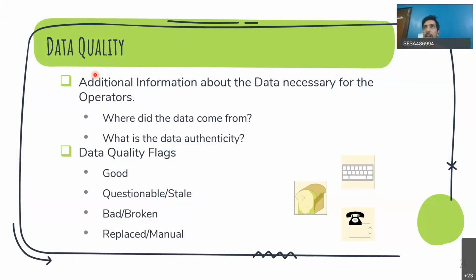For example, you get some value coming in from the field, and then suddenly, because of a communication issue, it's no longer communicating. But the past data, whatever came in last, is still shown. It may be correct or may not be correct, because during the loss of communication, the value could have changed. So the quality of that particular data may not be good.